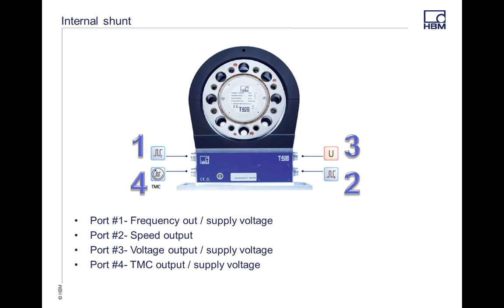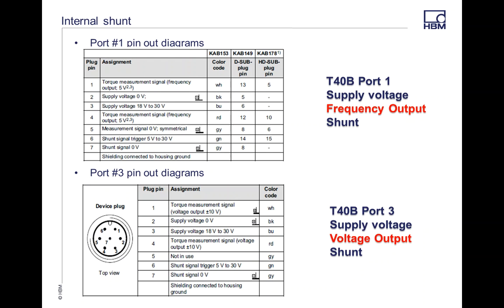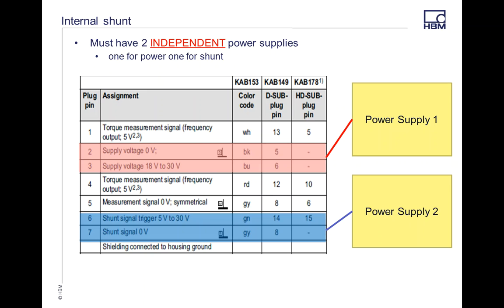Ports 1 and 3 are set up identically for the wiring configurations. This is a 7-pin set. On each one of the ports 1 or 3, not both, but port 1 or 3, you can supply a separate power supply voltage and turn on that shunt value. We suggest a separate power supply because it gets rid of any ground loops that could be in your system, and it also gives you a cleaner data signal, getting rid of some noise.